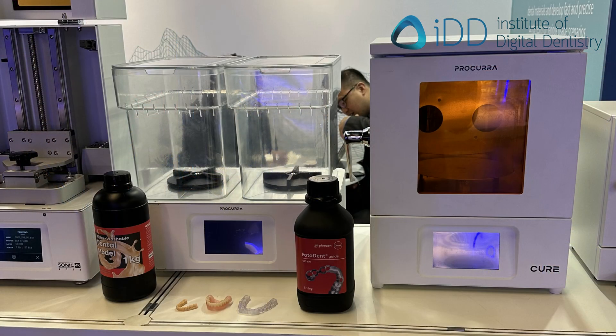I can see you've got what looks like some early prototypes of curing and wash units. Yes — for dental 3D printing, the print itself is only one part of the process. We still need to wash carefully following the FDA process and cure it completely to make intraoral applications safe enough. We've got our Pro-Wash, which has a two-station wash and automatic setup with different resin profiles we've validated. We also have curing units that can cure the parts, with a heating function and the ability to introduce nitrogen during curing so you can cure parts completely.